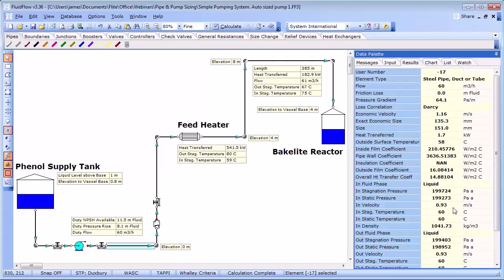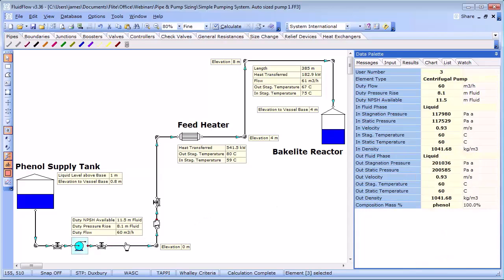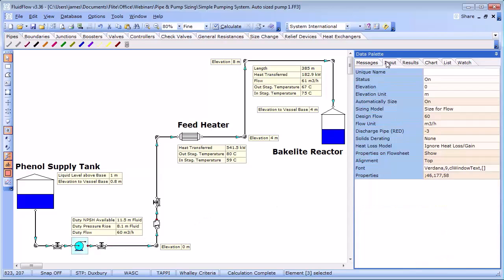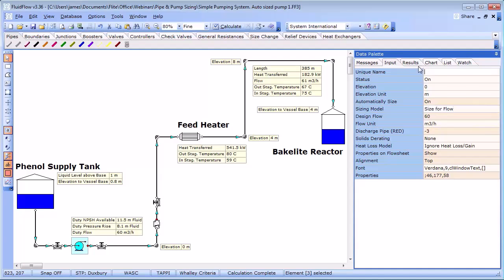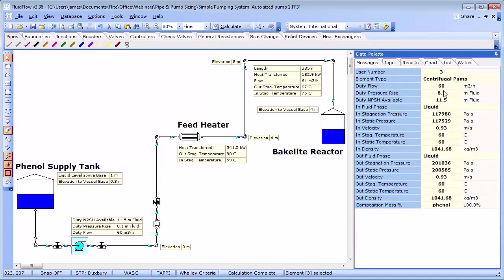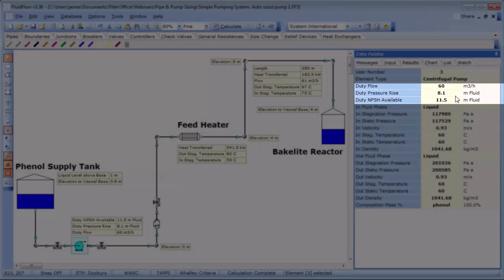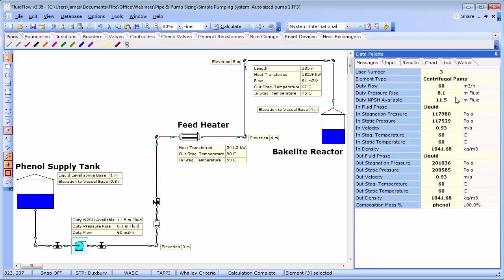Sizing the pump means specifying the head and flow at which the pump will operate. This is called the duty point and remember a pump will always operate where the pump performance curve and system curve intersect. The system loss calculation can be made quite easily using the automatically size function. We have set the design flow rate to 60 meter cube per hour. From the solution we can see that the pump duty pressure rise is 8.1 meters of fluid and the net positive suction head available in the system is 11.5 meters of fluid. We can also see that there is substantial heat loss in some of the pipes which we will revisit a little later.